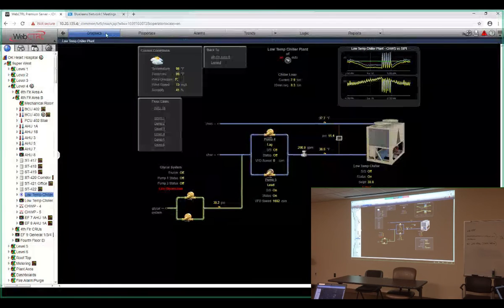So if that differential pressure is going up and coming down, is that just the drive controlling the pump? It's the drive controlling the pump, or the valve in that air handler changing position. Got it. I know Michael did mention there were a couple of these pumps where he wanted to look at the PID loop and how it's controlling, so that we may be seeing that from the drive. All right.